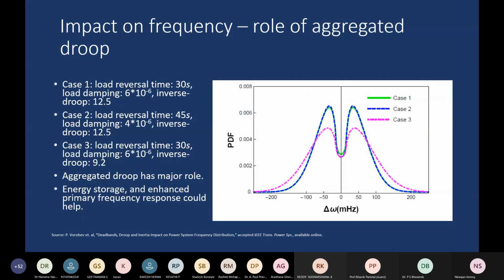Similarly, there is something called load reversal time. If you look at the general load on the power grid, I'm not talking about the load at a particular bus, but the amount of load in the entire grid. You just sum up the entire load of the system. How do you do that? The entire load of the system cannot actually be measured. What can be measured is the amount of generation. In the mess, how many rotis are eaten by everybody cannot be measured. However, how many rotis are being cooked in the kitchen can be measured. So the load is estimated from the generation.